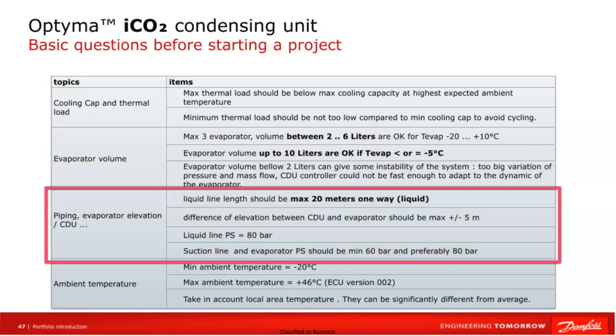Piping. Depending on the location of the evaporator, appropriate piping parameters should be taken into account, such as pipeline length, maximum 20 meters. Elevation difference up to 5 meters. Working pressure of the liquid line is 80 bar. Suction line and evaporator with PS pressure of 60 bar, preferably 80 bar.